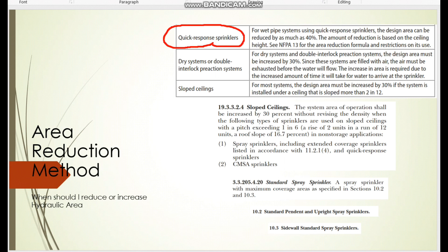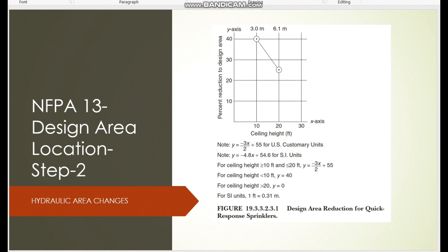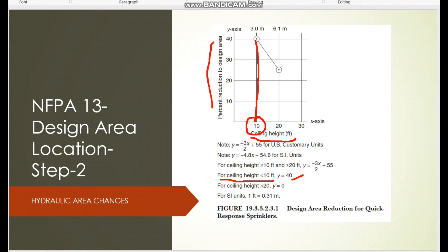The amount of reduction is based on ceiling height. Looking at Table 10, the x-direction shows ceiling height and the y-direction shows percentage reduction to the design area. For a ceiling height less than 10 feet you can reduce up to 40 percent — for example, from 1500 square feet you can reduce 40 percent. For a ceiling height more than 20 feet you should not reduce anything and must keep the area as-is.